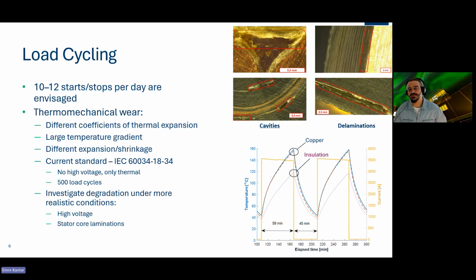So the more start and stops, the more temperature gradients, meaning we are expecting more delaminations and cavities being formed in the insulation. To mimic this, in this setup we increase the temperature, and when it hits the maximum temperature that the insulation class can withstand, we immediately start cooling it down and then repeat it. One cycle, as you see here, takes almost 2 hours, and then we achieve one start-stop like in laboratory conditions. And then we just continue like that.